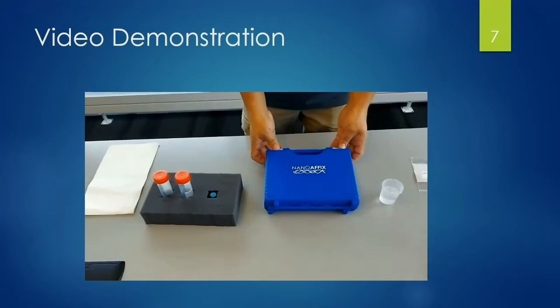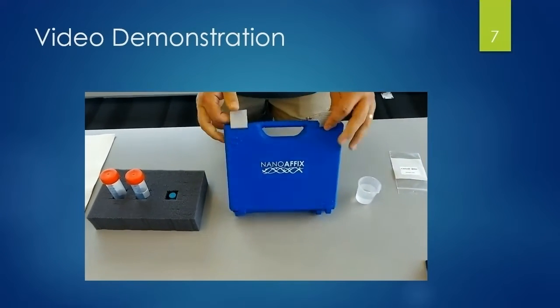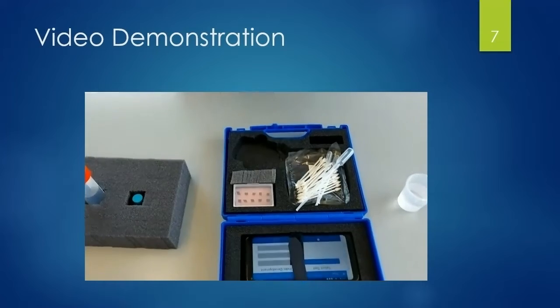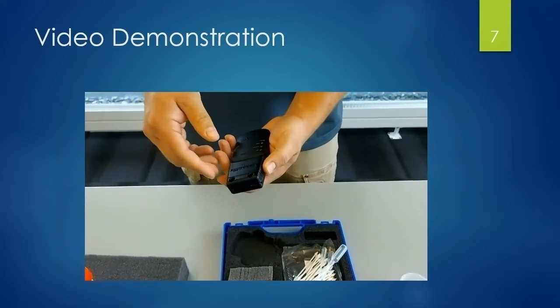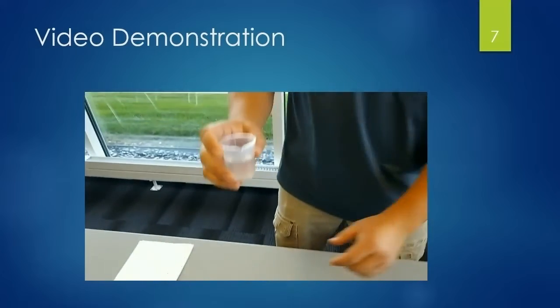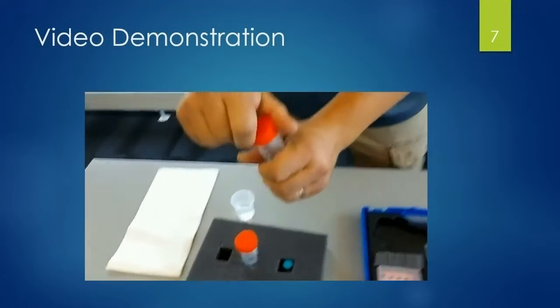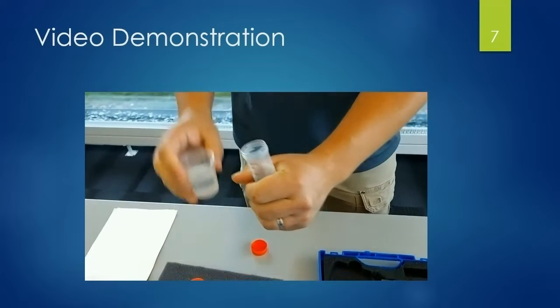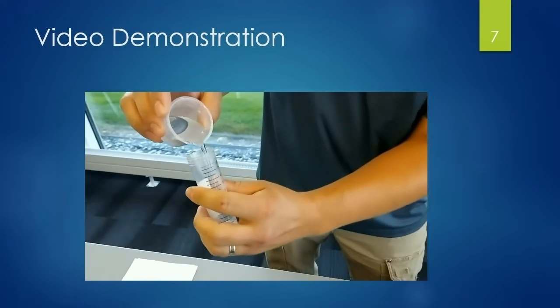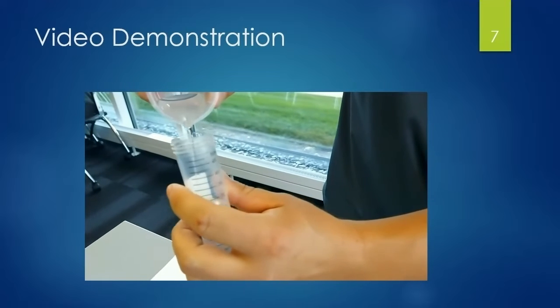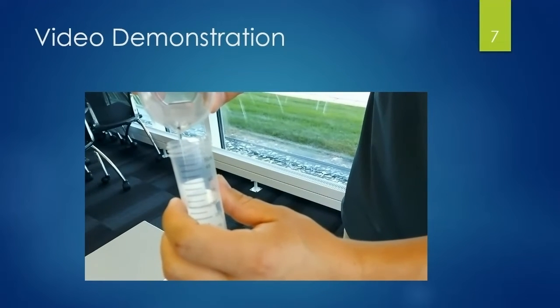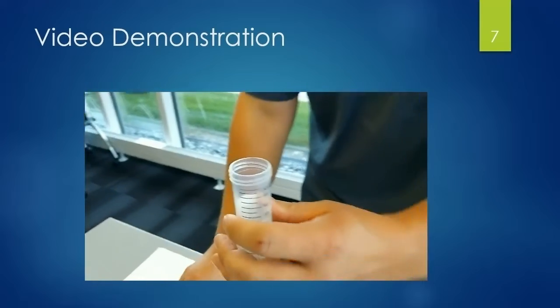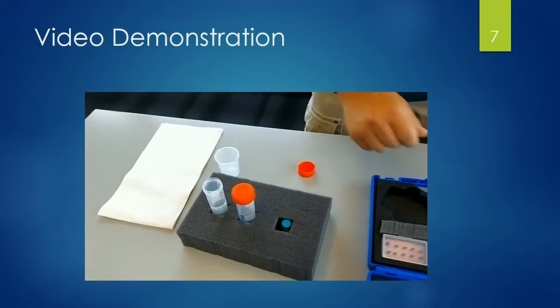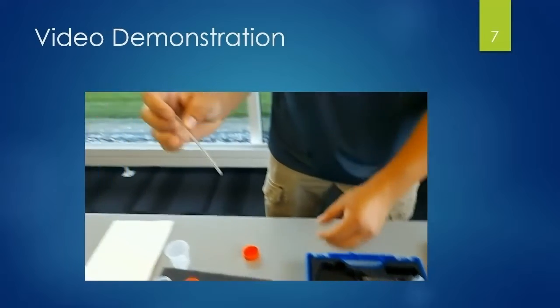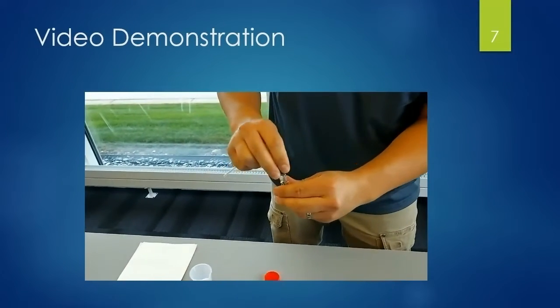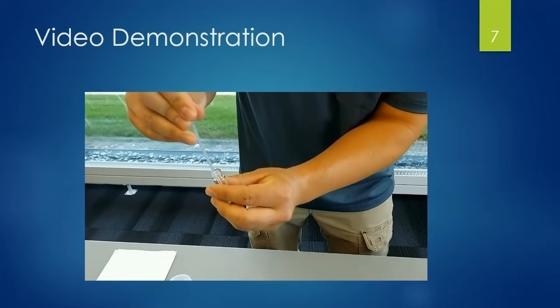Next, I'd like to show a brief how-to video of our device. It comes in a rugged carrying case to easily take it out into the field and collect measurements on site. The first step is collect a water sample from some source, such as your kitchen sink. Next, add that to the test tube. If you'd just like to test for soluble lead, the sample could be immediately added to the sensor. Or if you'd like to get a total lead reading, a combination of soluble and insoluble lead, we'll need to add our lead digestion solution to the mix and let that react for about 10 minutes.